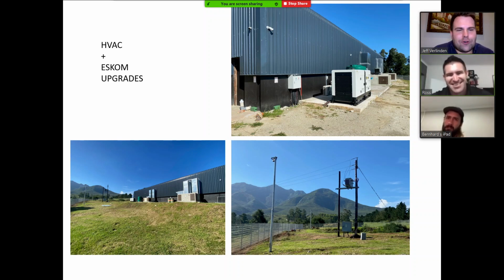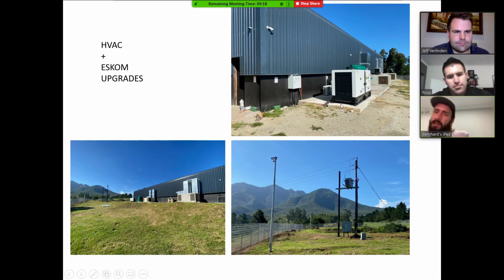In terms of electrical power generation support, how much kVA are we generating on the system? I've had to upgrade the transformer. Originally there was a 25 kVA transformer on the farm, and I had to upgrade it to a 250 kVA. That doesn't mean my facility is drawing 250 kVA, but I put a big enough transformer in so that when I build a greenhouse in the future, it can power that as well.